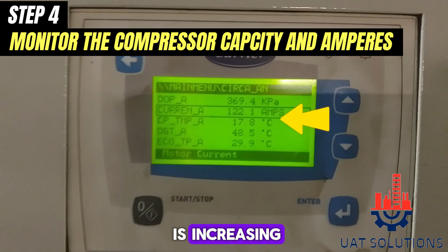As the chiller increases the capacity of the compressor, the current should increase also. If only the current is increasing but the compressor capacity is not increasing in the display, this indicates that the compressor capacity control system is not functional.